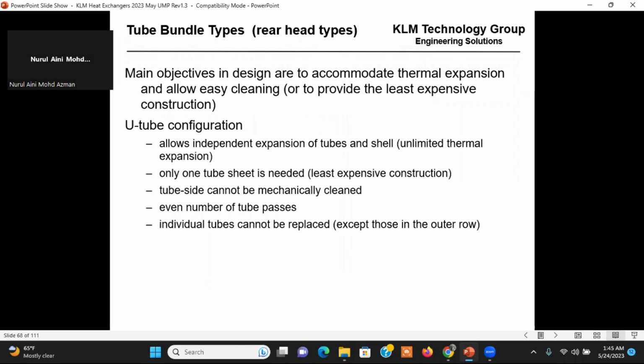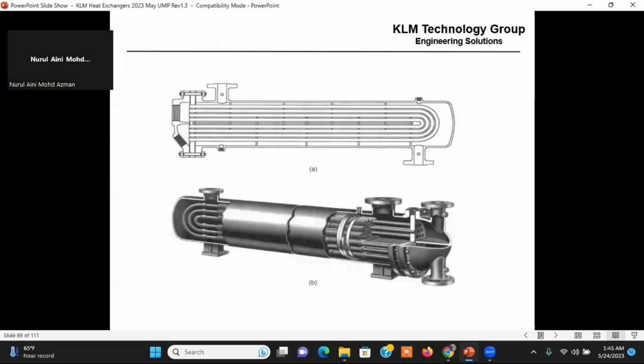Bundle types, rear heads, U-tube configuration. The main objective is designing to accommodate thermal expansion and allow for easy cleaning. So I typically use the U-tube. All right. It allows for independent expansion of tubes in the shell. Only 1 tube sheet is needed on the very front. And an even number of 2 passes in the tubes, except those in the outer row. So this is what I typically design. This is the front. It's got a U-tube. And it goes in the top and out the bottom. So for hydrocarbon service, this is what I design.